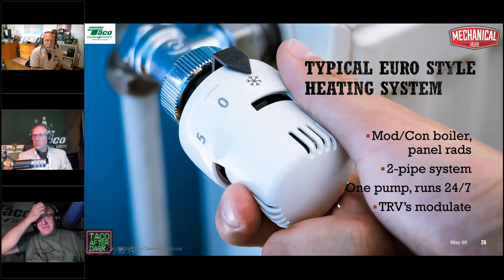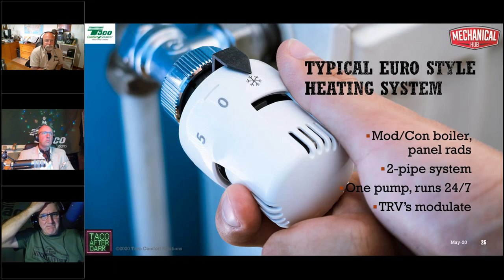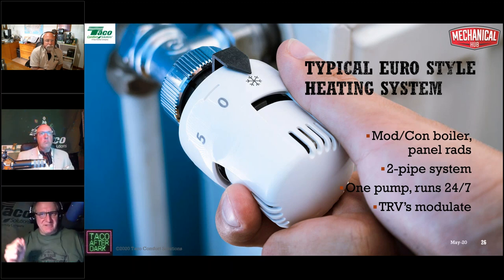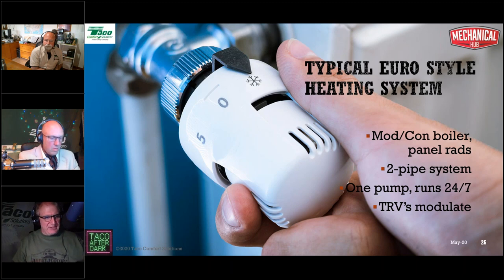So let's talk about where it came from. Both came from your typical European style heating system. A typical European style heating system has large panel radiators in each room. In most cases, it's a two-pipe system, meaning a supply and return to each radiator: a supply to one radiator, then a dedicated return right back to a central manifold. It's almost like a home run system, if you will, for each radiator. The output of each radiator is controlled by a thermostatic radiator valve. The thing that is tasked with maintaining the comfort level in the room is about an inch and a half to 2 inches away from the hottest thing in the room. But hey, what do I know? It's kind of just what it does.